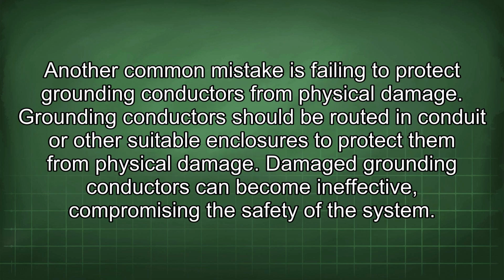Another common mistake is failing to protect grounding conductors from physical damage. Grounding conductors should be routed in conduit or other suitable enclosures to protect them from physical damage. Damaged grounding conductors can become ineffective, compromising the safety of the system.